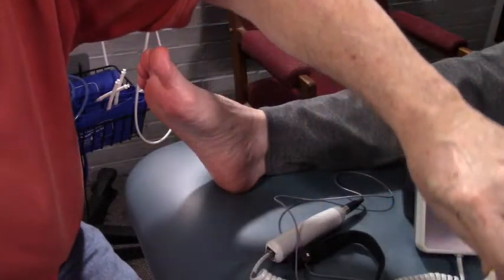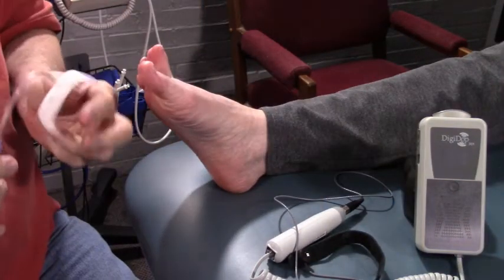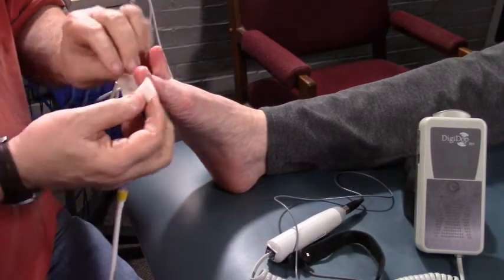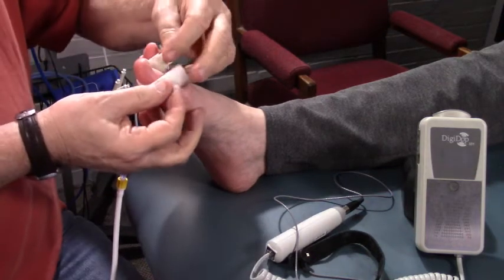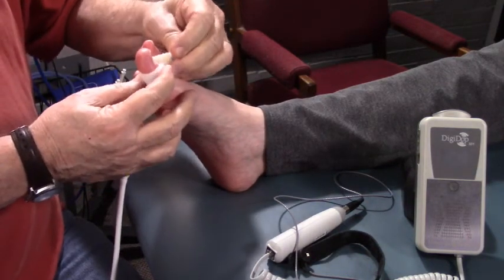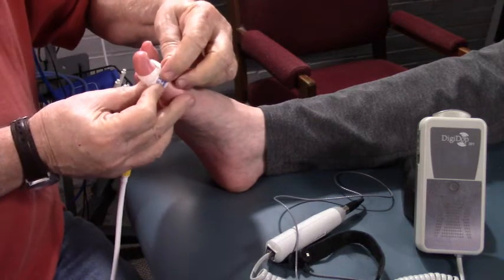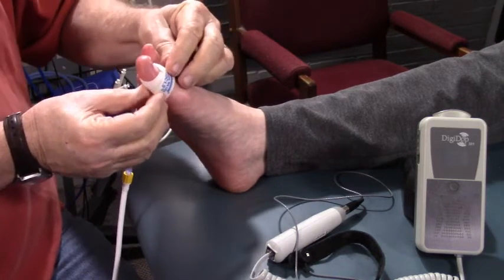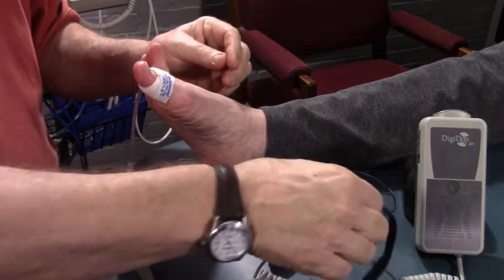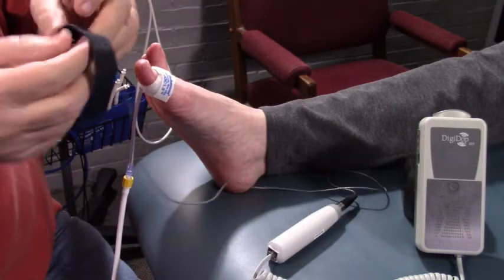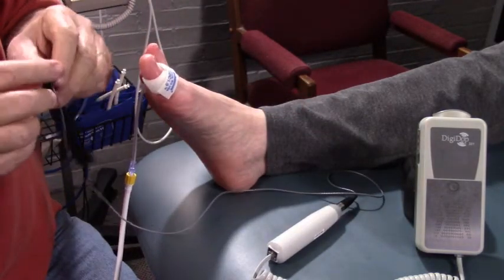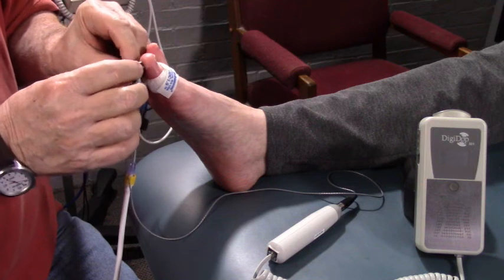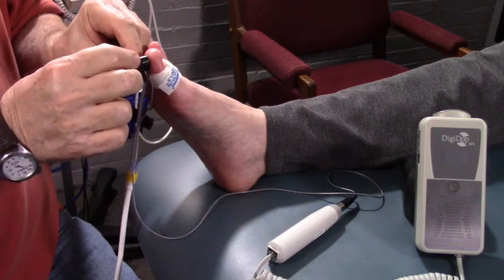Place the toe cuff with the yellow ankle toe hose connector attached to it on the great toe, making sure it fits well toward the base of the toe. The PPG sensor should be placed against the pad portion of the great toe and securely attached with a Velcro strap so that no light can be detected by the sensor.